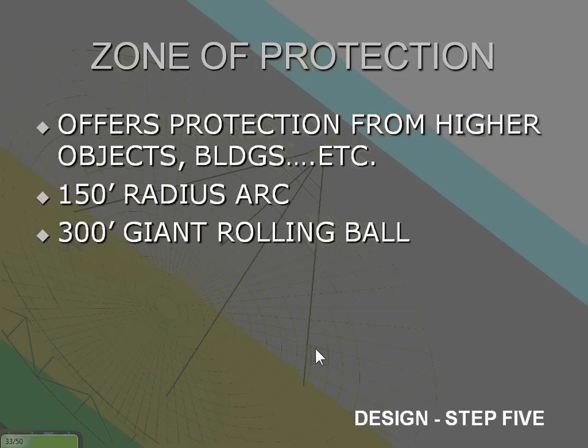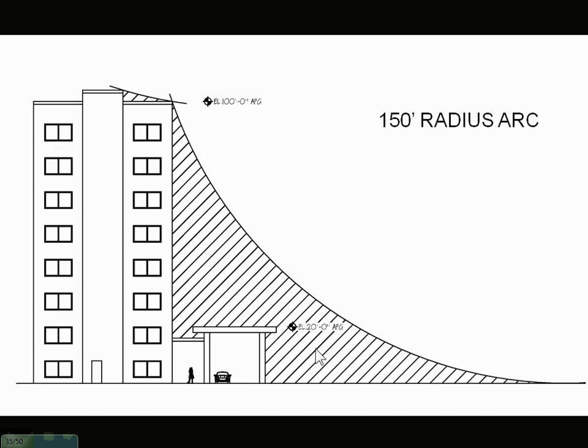I don't know if you guys are familiar with CAD, but basically if you were to draw a 300-foot tall giant rolling ball, this is what it would look like. What you can end up doing is just take that ball, push it up next to the building, and I can guarantee without any instance that this area here that's hatched will not get struck by lightning. It's a mathematical equation. They've done extensive research on where lightning actually hits. If I have an air terminal up here, there's an arc that it creates to ground where there's no way lightning can actually hit. So that's how we decide what zone of protection you get from higher adjacent buildings.